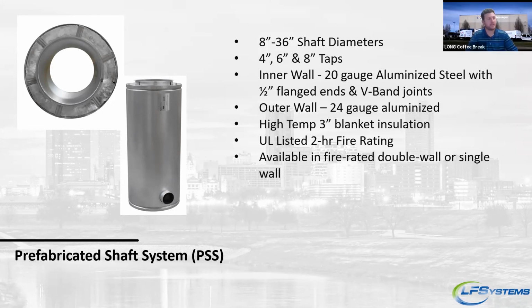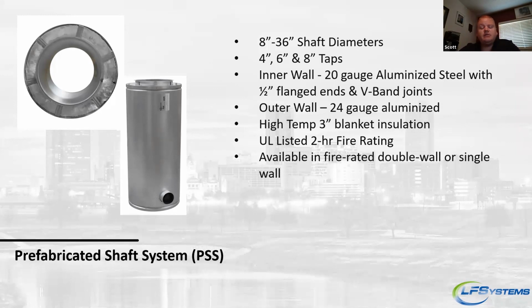Is there a special enclosure we have to put around this fire rated shaft, or can it run bare? It can run bare. You can run it inside the stairwell. You can run it exterior of the stairwell. You can leave it exposed. It is actually a 2-hour rated shaft and duct all in one. So you don't have to do anything but put this together. And if you're running it exterior, like I said, leave it exposed or put a facade around it.